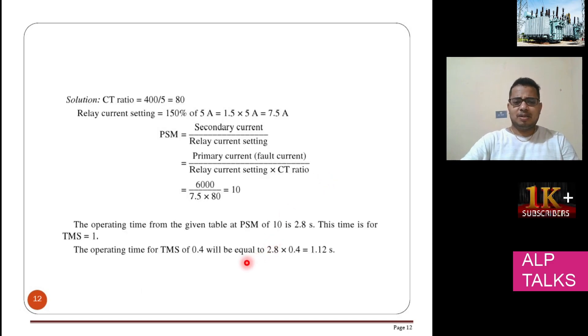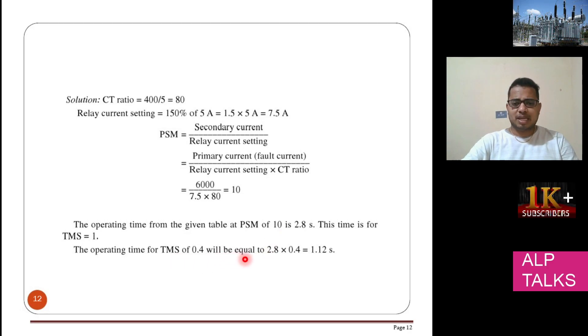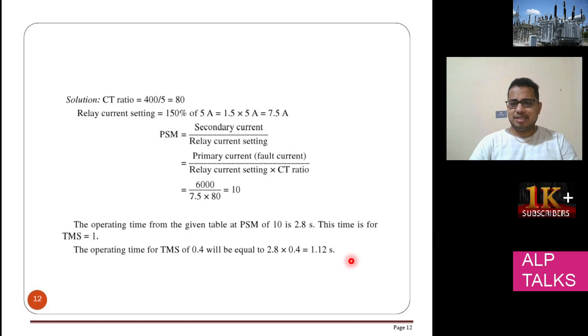The operating time with TMS of 0.4 will be 2.8 × 0.4 = 1.12 seconds. This is one of the basic problems that gives you an actual feel of how the relay operates.